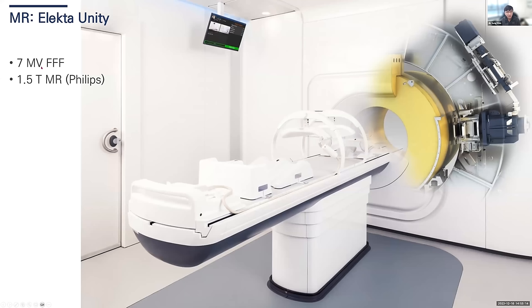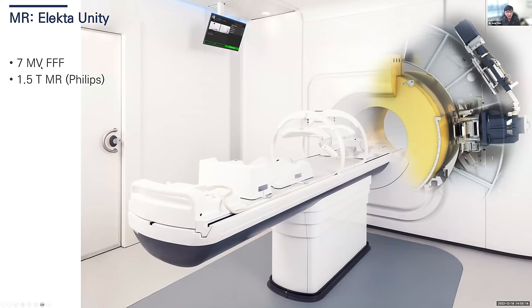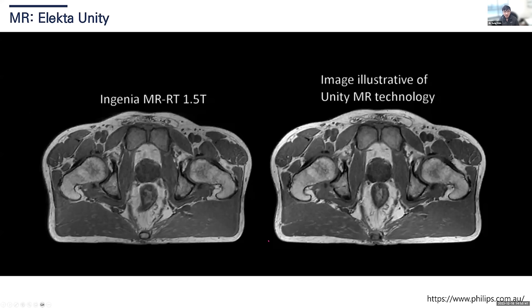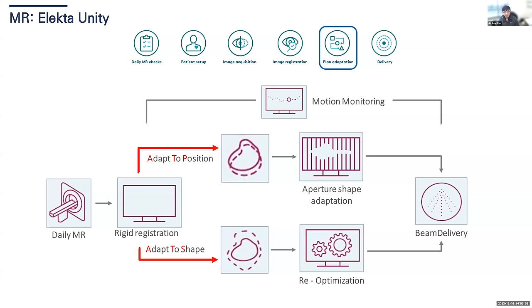The Elekta Unity has a 7 MV flattening filter-free X-ray with a 1.5 Tesla Philips MR. The advantage is you can easily see soft tissue during treatment. You can clearly see the prostate and other soft tissue — totally different from CBCT or KVCT. The Unity offers two adaptation processes: ATP (adapt to position) and the more difficult ATS (adapt to shape), which requires re-optimization for the best plan.